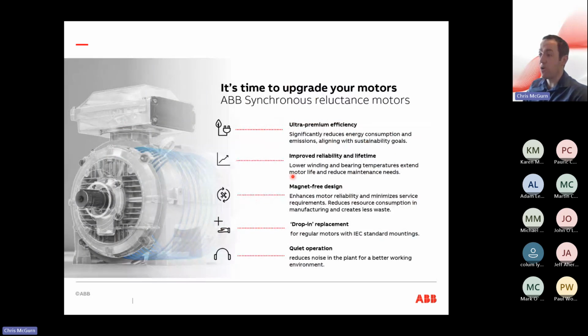Another little thing I'm going to talk to you about is the ABB synchronous reluctance motor. Whereas the regulations themselves only go to IE4, and IE4 is the minimum requirement for motors between 75 kilowatt and 200 kilowatt, there are even more efficient motors out there. Some typical end users aren't happy with meeting just the minimum requirements of that legislation. They want to push out and look for the most efficient that they currently can, to reduce their bills, to put them at the forefront of efficient technology. And that would be, with ABB, our synchronous reluctance motor.